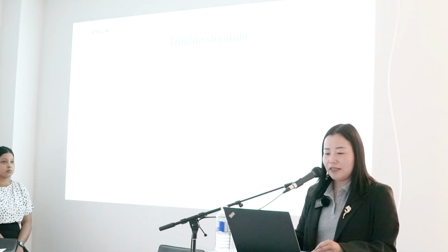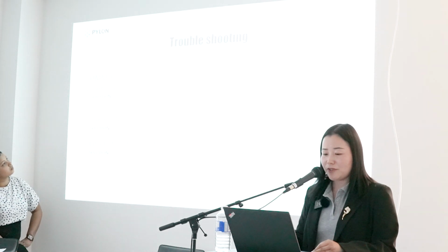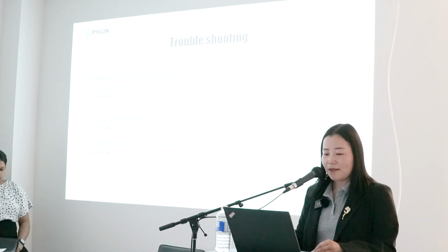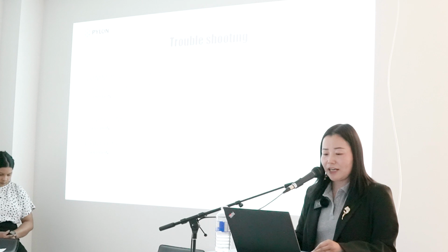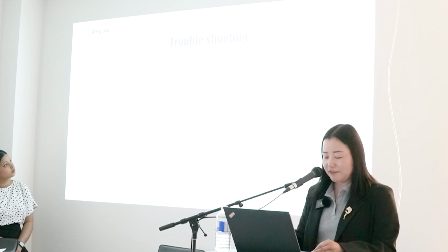If there's a communication-related problem, it might be the baud rate selection. Just check dip switch 1 on the battery. If the baud rate of the communication is 9600, dip switch 1 should be 1. If the baud rate is 115200, dip switch 1 should be 0. And check the cable connections, including the communication methods and link ports. For the pin definitions of communication cables, please refer to the definition diagram.